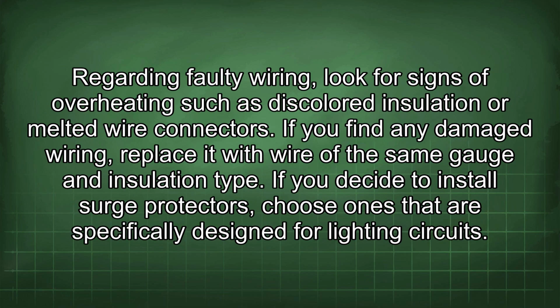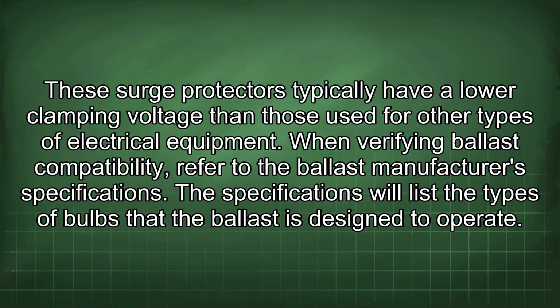Regarding faulty wiring, look for signs of overheating such as discolored insulation or melted wire connectors. If you find any damaged wiring, replace it with wire of the same gauge and insulation type. If you decide to install surge protectors, choose ones that are specifically designed for lighting circuits. These surge protectors typically have a lower clamping voltage than those used for other types of electrical equipment. When verifying ballast compatibility, refer to the ballast manufacturer's specifications. The specifications will list the types of bulbs that the ballast is designed to operate.